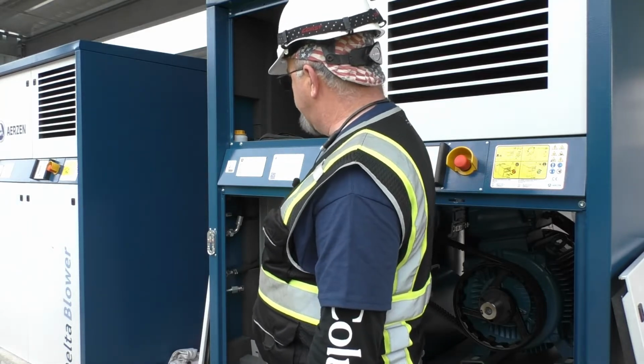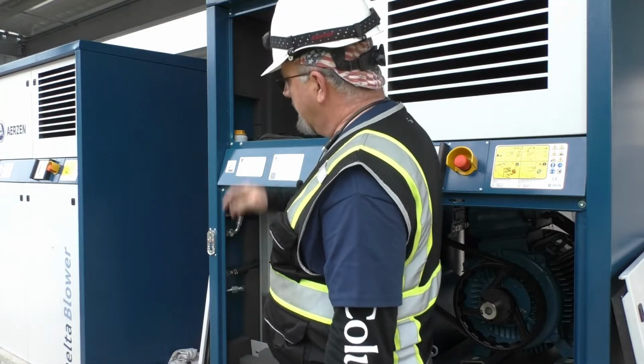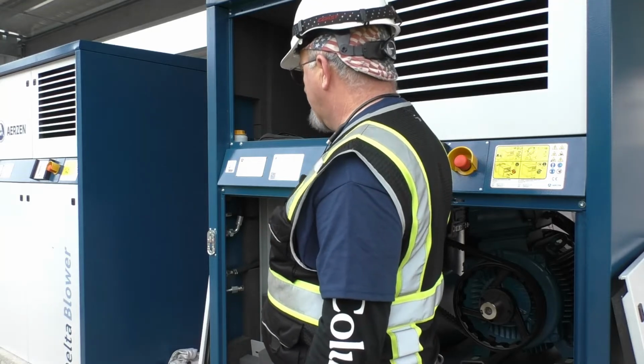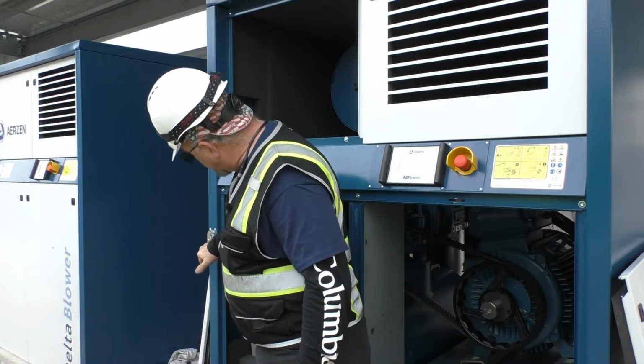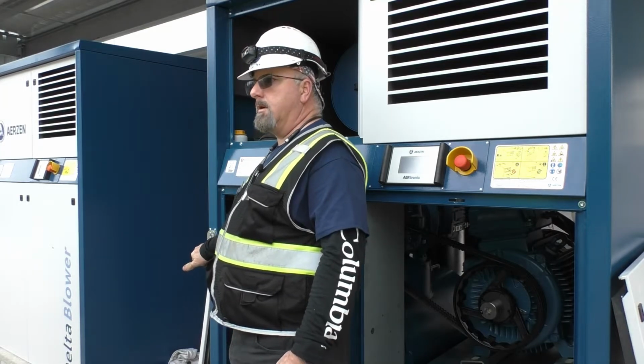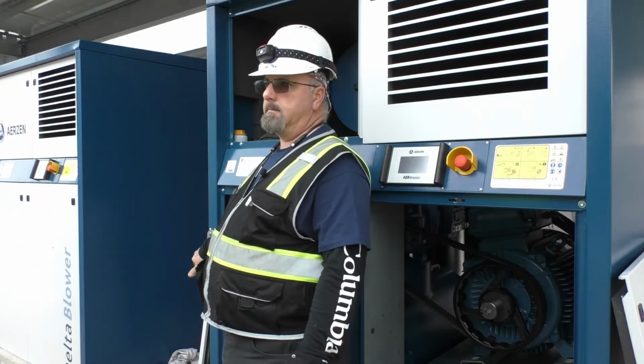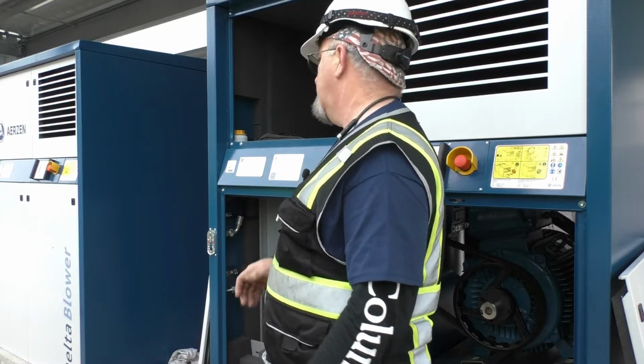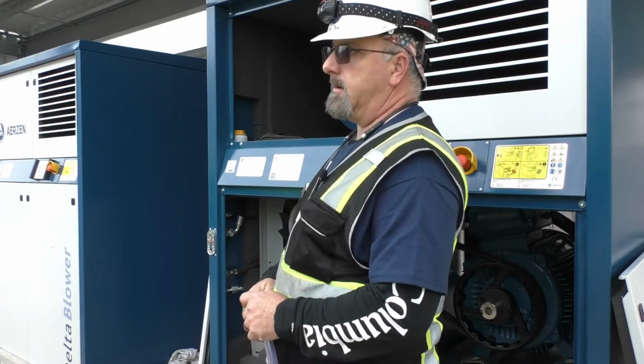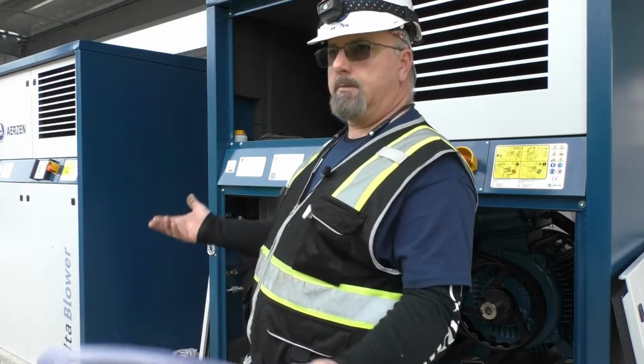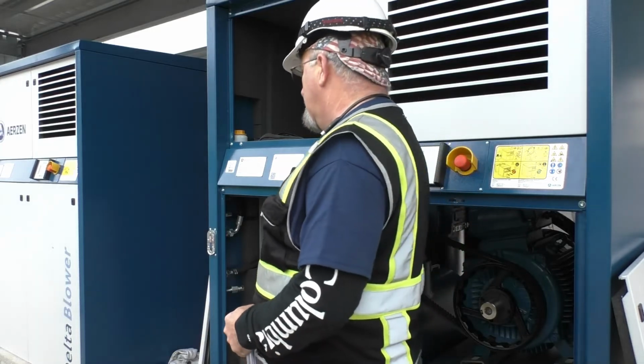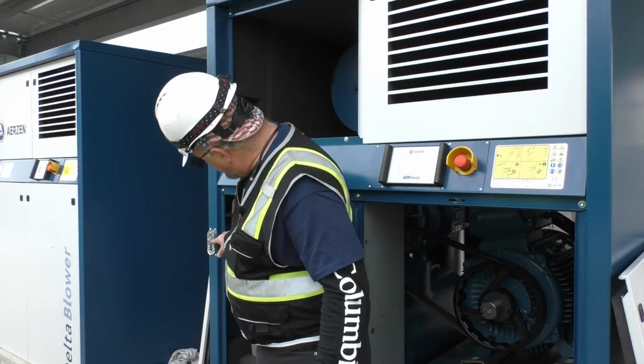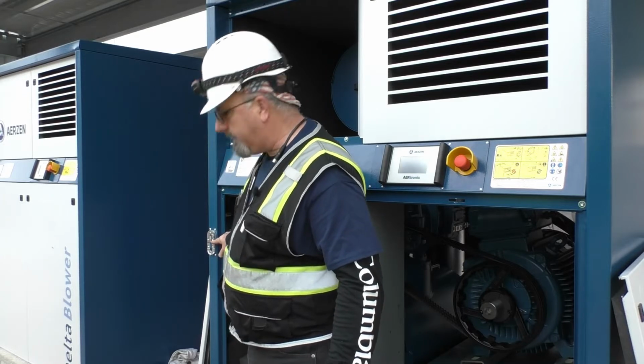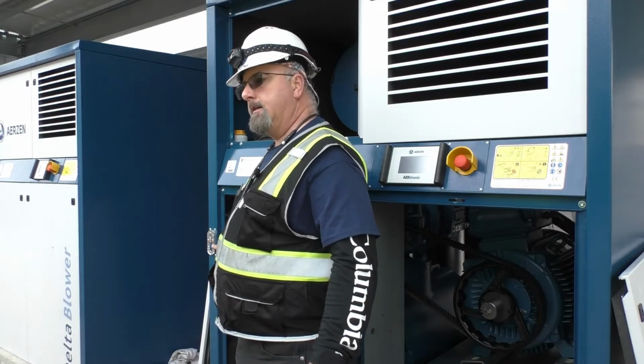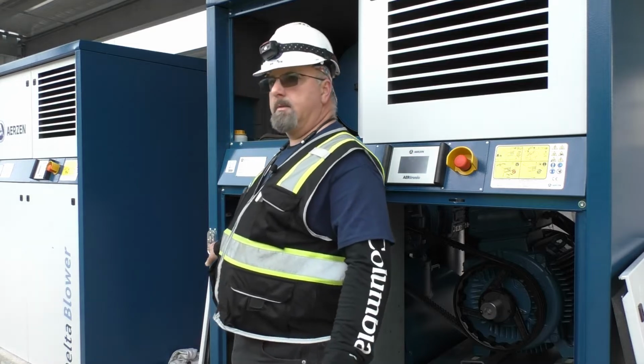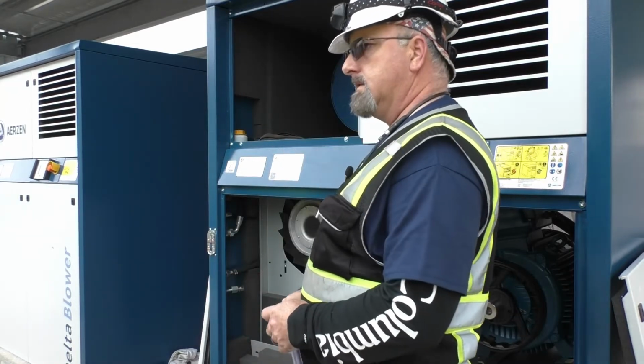Once you're ready to fill it back up, take your cap off. And now as you're filling it up, once you start getting oil into the sight glass and it starts coming up towards your mark, you will definitely want to slow down, because once you reach that point, it doesn't take much more to finish topping it off. So if you overfill it, guess what? You have to drain some out. So bring it up to, like I described on the circle, you have a fat line for the high, a fat line for the low, and then the thin line in the middle equals the dot on the stage.